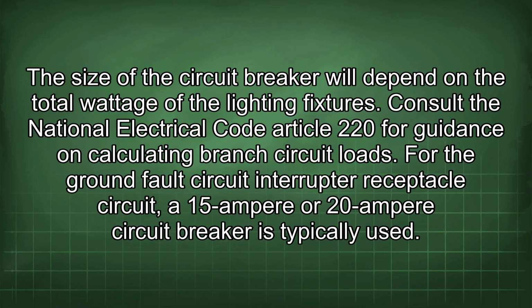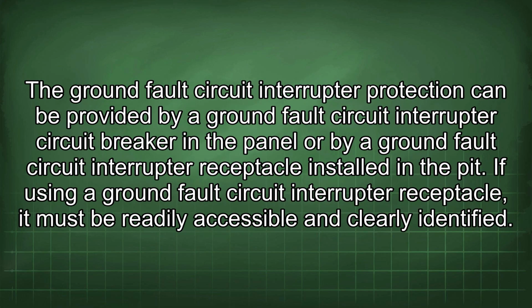For the ground fault circuit interrupter receptacle circuit, a 15 ampere or 20 ampere circuit breaker is typically used. The ground fault circuit interrupter protection can be provided by a ground fault circuit interrupter circuit breaker in the panel or by a ground fault circuit interrupter receptacle installed in the pit. If using a ground fault circuit interrupter receptacle, it must be readily accessible and clearly identified.